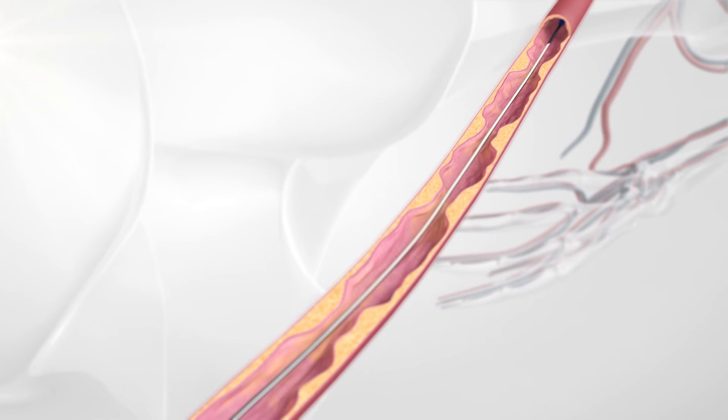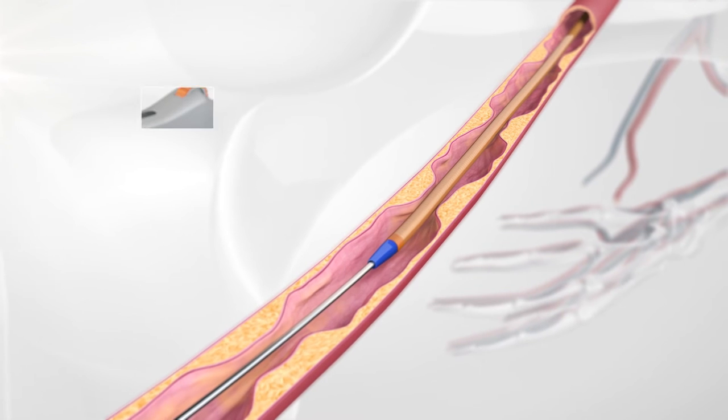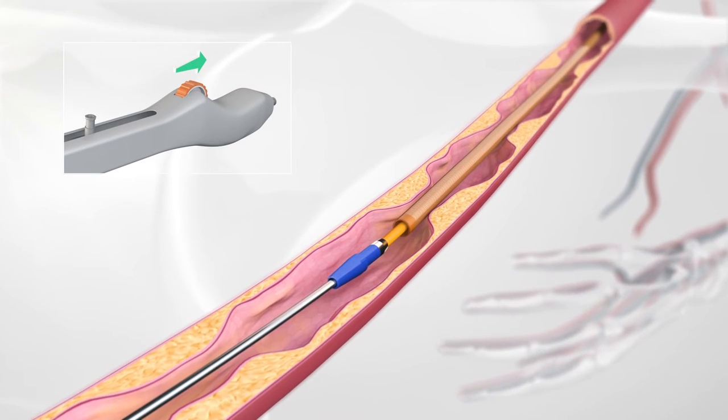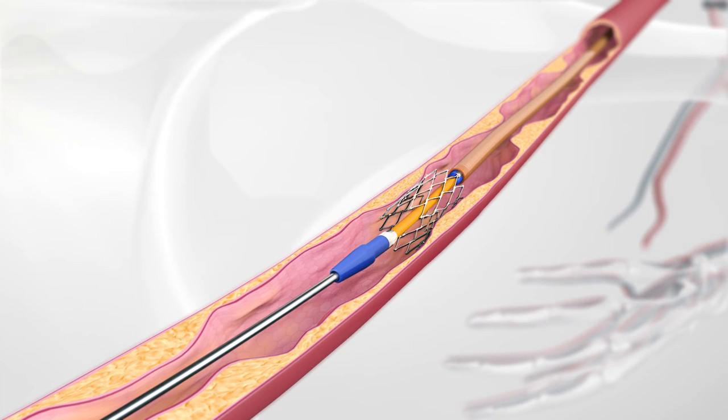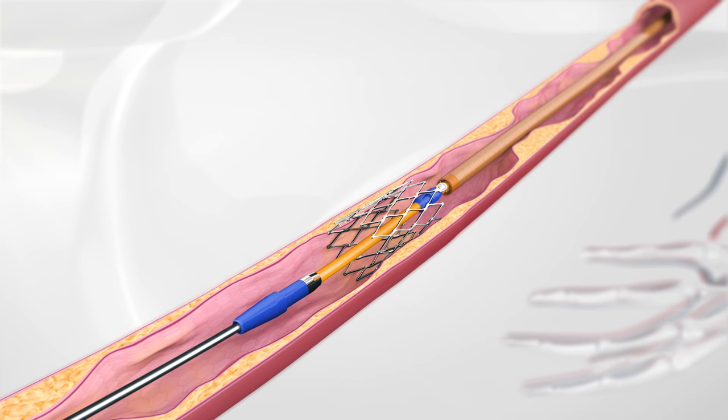After pre-dilatation with a balloon catheter, the first short stent can be implanted. By turning the wheel on the handle, the stent is released into the lesion of the vessel. The stent is completely released once the marker band is unlocked from the mount point.